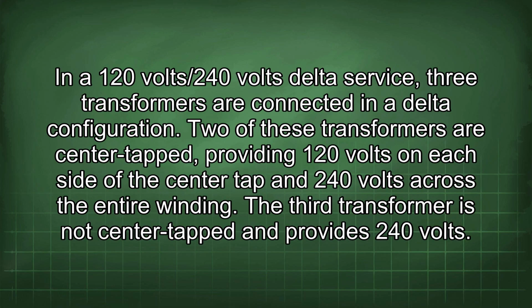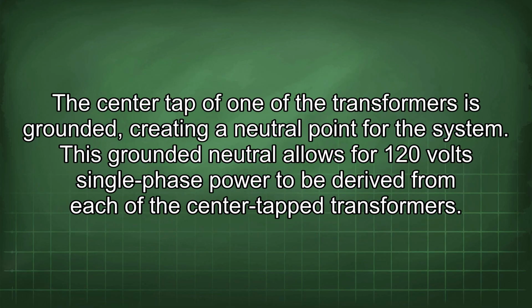In a 120V/240 volts delta service, three transformers are connected in a delta configuration. Two of these transformers are center tapped, providing 120 volts on each side of the center tap and 240 volts across the entire winding. The third transformer is not center tapped and provides 240 volts. The center tap of one of the transformers is grounded, creating a neutral point for the system. This grounded neutral allows for 120 volts single-phase power to be derived from each of the center tap transformers.